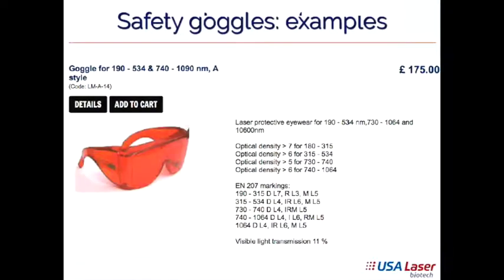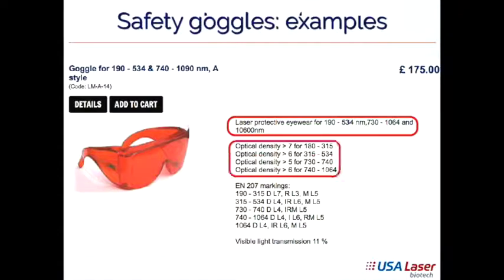Let's look at another example. This is the other one I showed you before, multiple ranges. It will show you that right on the website: laser protective eyewear, 190 to 534, 730 to 1064, and 10,600 by itself. And then it has the optical density, again with different values: 7 for the low, the UV section, 6 for the 315 to 534, which is not useful for therapy. But it's 5 for 730 to 740, just a short range. This one, that's a nice one. It has from 740 to 1064 an optical density of 6. So that's good.